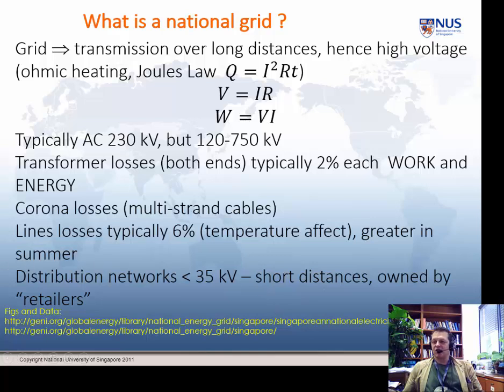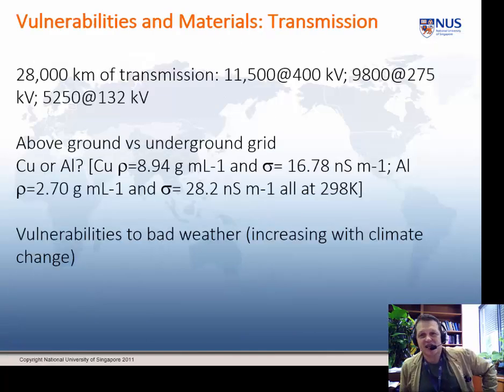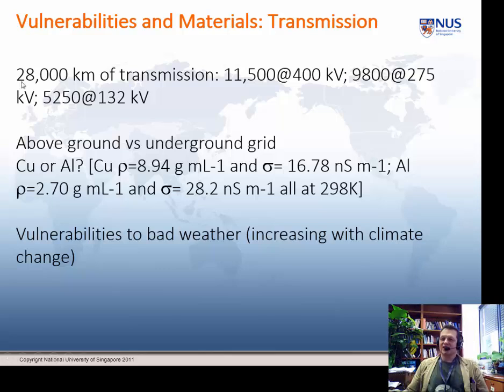Distribution networks, as I said before, are not the main national grid. They are smaller affairs, and they only run at 35 kilovolts, not 230. And they're typically over short distances. And they're usually owned by the people who sell you the electricity. Okay, so let's think a little bit about types of vulnerabilities. We've already talked about above ground and underground. We've talked about copper and aluminium, where you're trading off weight versus conductivity, basically. Above ground means you're vulnerable to bad weather. And remember, violent storms are predicted to increase under climate change. Underground, on the other hand, you're protected from that, but you are vulnerable to flooding. So you pay your money and you take your chance, depending on which climate regime and which events you think are most or least likely.